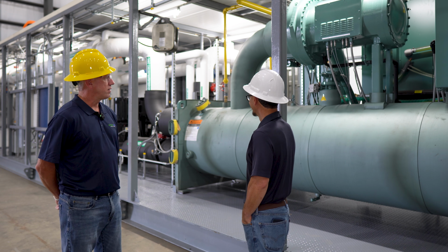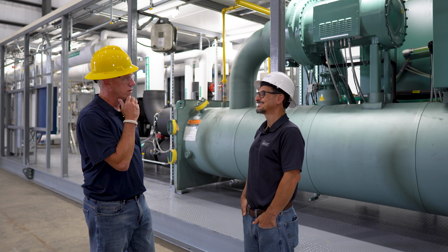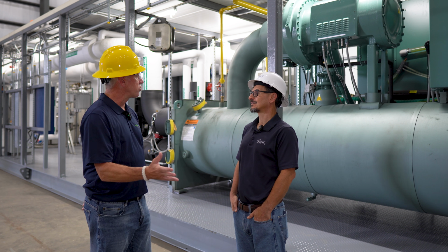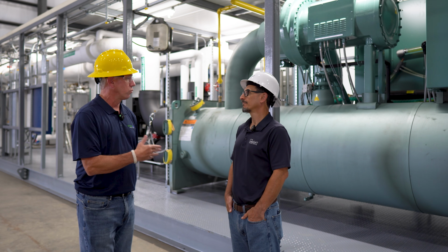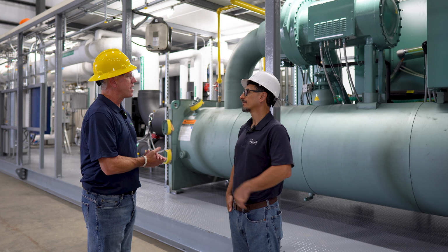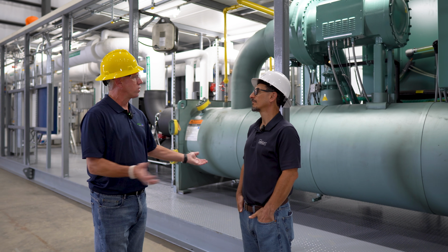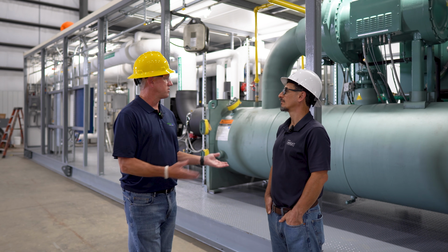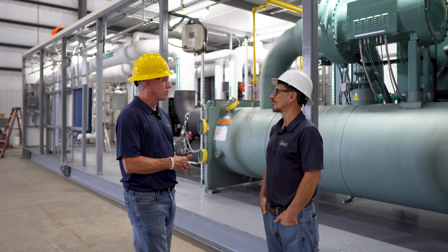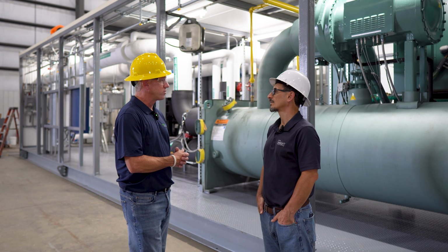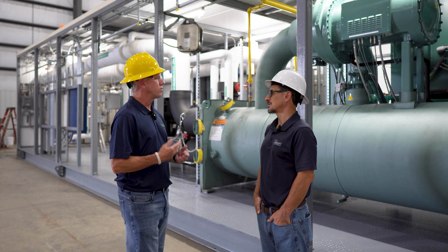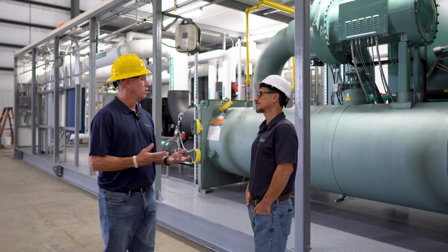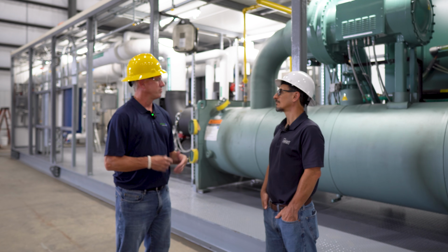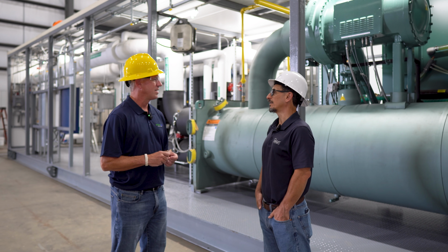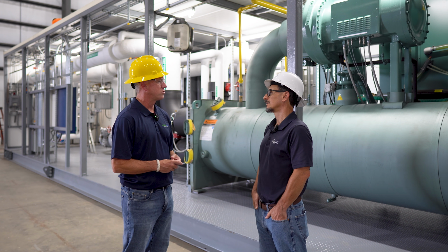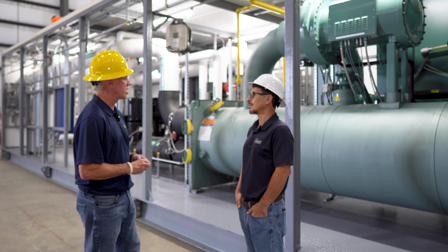How about that? Well, I'm glad you brought that up, because with the different refrigerants that are in there, that's what got clients. We kind of let one slip by us. We had a client where we ordered a new chiller. All the existing chillers in the field were 134A. The next one they shipped out was a 513. You had to have different sensors, different sensors for different monitored refrigerants, device right. So, you know, you learn from your mistakes. Yeah, that's how you get better at it too. So we educated our process to always check that when we're going through a checklist. That's what it's all about.